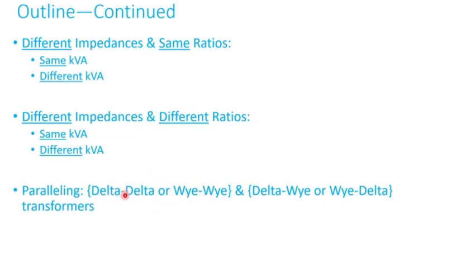Delta-delta or wye-wye basically have zero phase shift between the primary and secondary. These cannot be put in parallel with delta-wye or wye-delta because delta-wye or wye-delta have an inherent 30-degree phase shift.